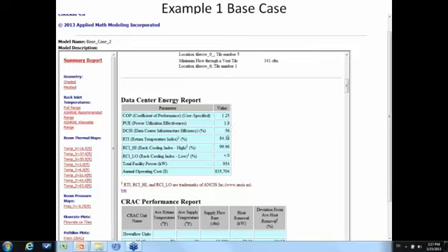But take a look at the RTI number right here, Magnus, 84%. Now, what's that telling us? It's telling us that we've got net bypass airflow here, right? That's correct. If it's below 100%, it means that we have a bypass there. And of course, that's not good, because if you have bypass there, we are funneling through too much air to the space, and depressing the return temperature back to the air handler, so the efficiency of that system will not be at the peak. That's correct.